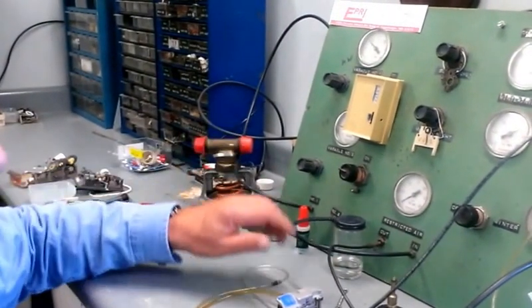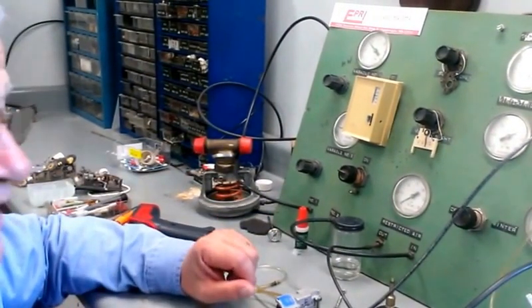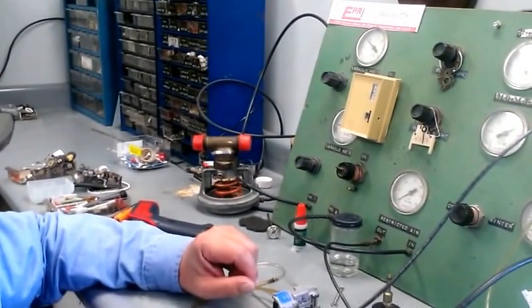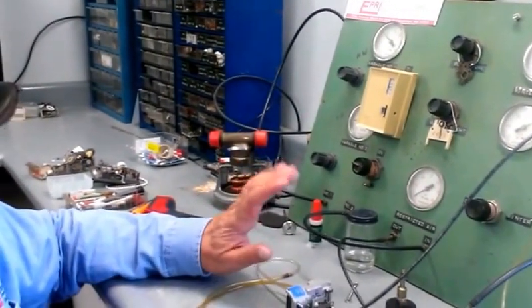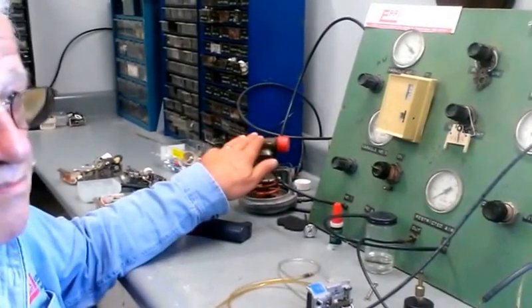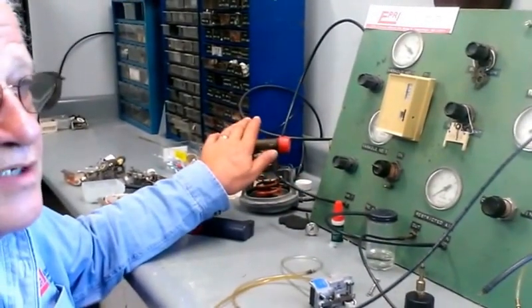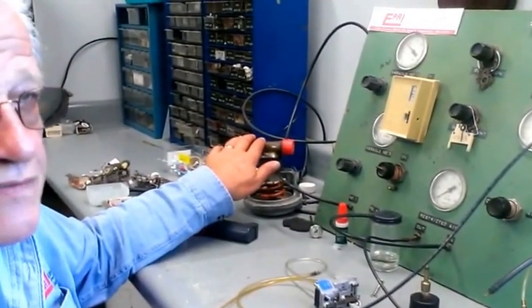So if your thermostat, once you're calibrated, can't handle the volume or the bleed rate, you know that you have a problem. There's other problems you can have, but certainly that's a big problem, and it's a big reason we see controls come in to us for repair.